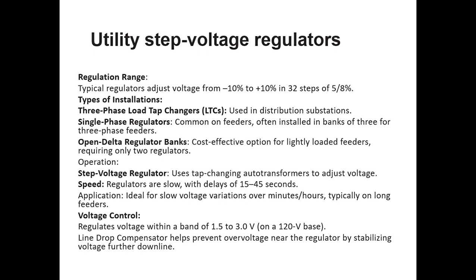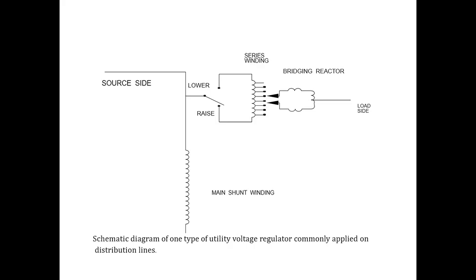Voltage control regulates the voltage within a band of 1.5 to 3 volts on a 120 volt base. The line drop compensator helps prevent over-voltage near the regulator by stabilizing voltage further downline. So these are the utility step voltage regulators. Now here there is a diagram. This is a schematic diagram of one type of utility voltage regulator, commonly applied on distribution lines, at the distribution level. We connect to the series winding, then there is a bridging reactor, and the source side and load side. We can choose a particular tap so that we get a proper voltage at the load side. The process is the same as that of an OLTC, the on-load tap changer, or OFTC. We choose different taps so that we get proper voltage regulation.